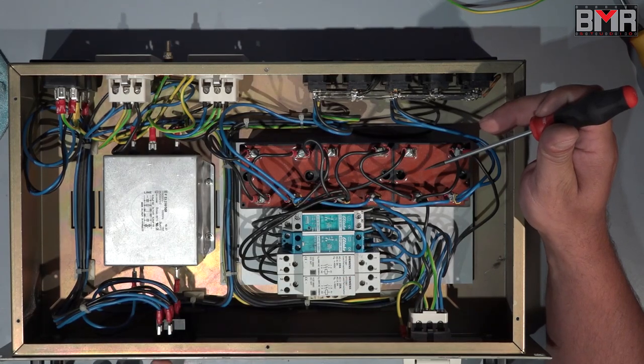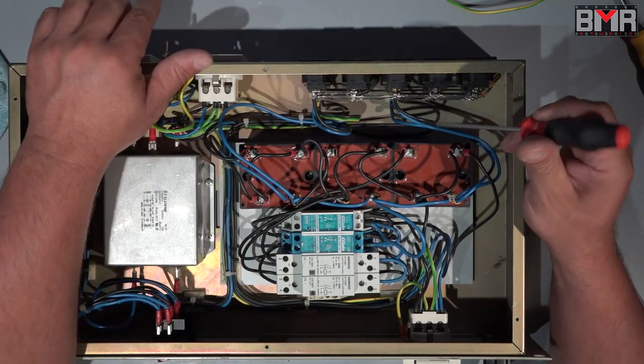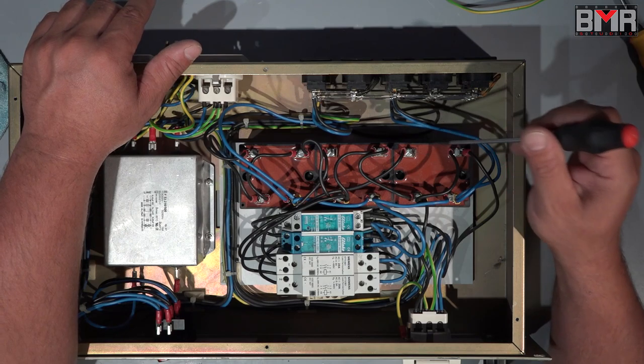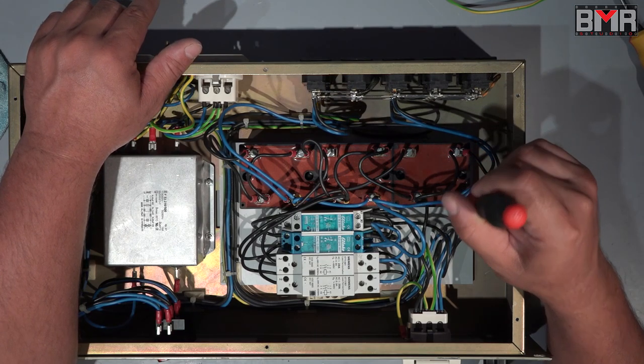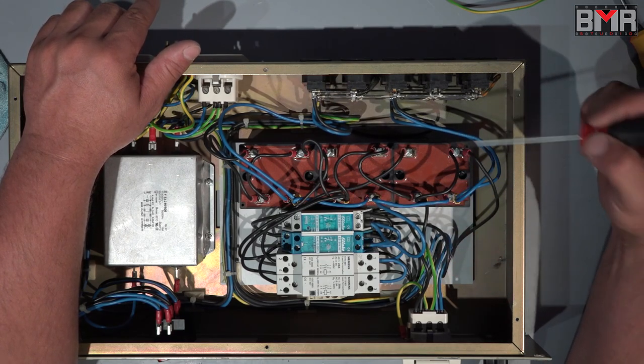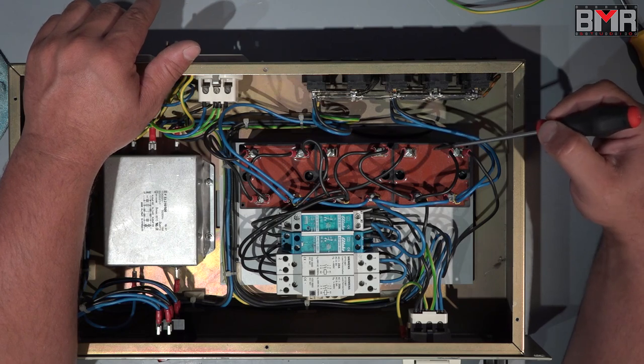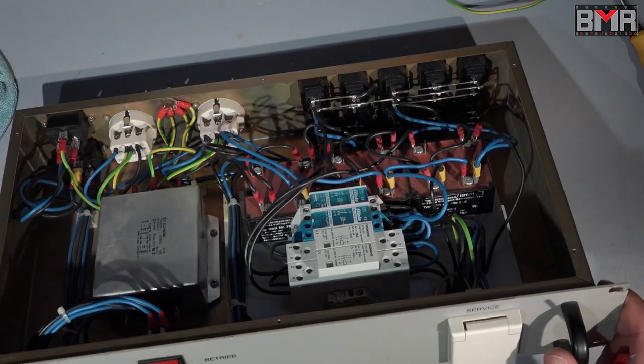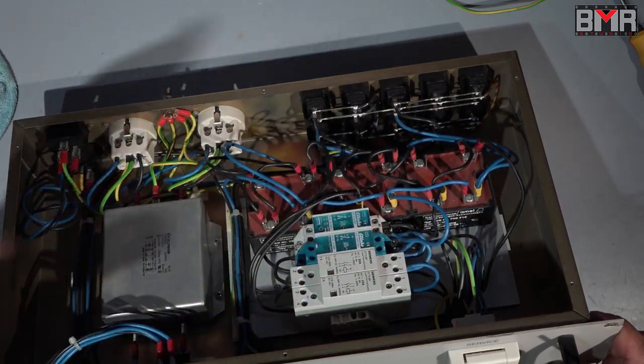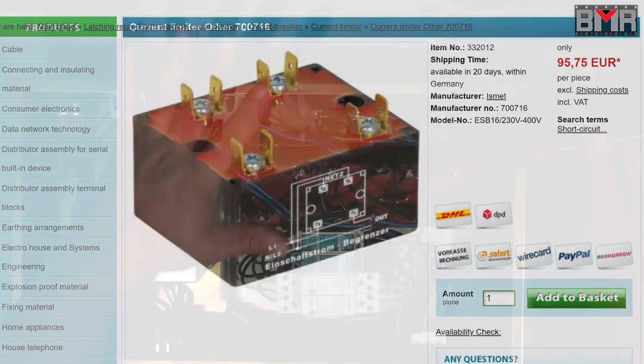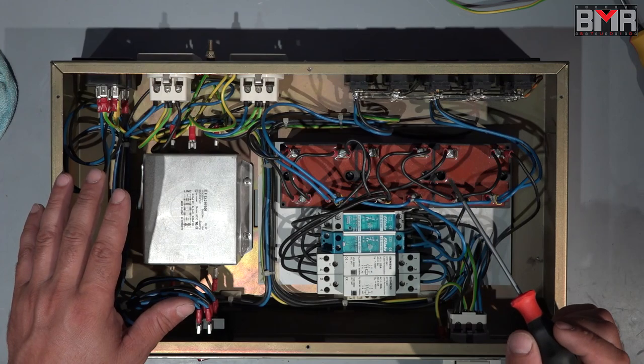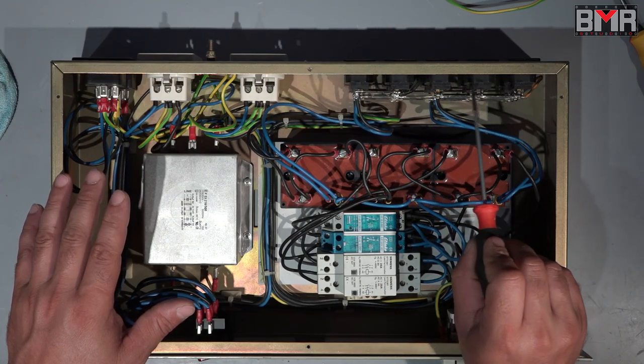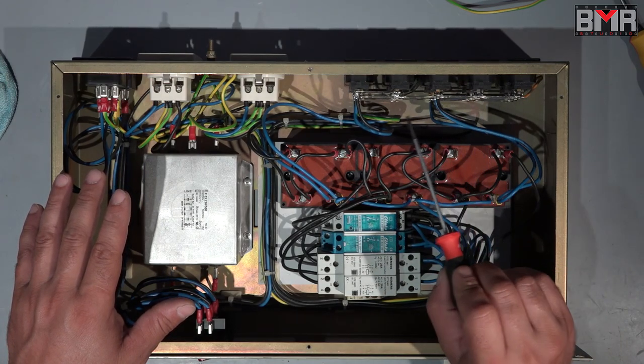Why? Because the NTC resistors, they have a magic behavior. So a normal resistor, if you heat them up, of course, you increase the resistance. Now with the NTC resistors, this is completely opposite. So as the temperature is rising, the resistance will go down. So this is how this NTC can do this really nice ramp on the beginning of the switched power. And after 50 milliseconds, of course, this mini computer here inside will short out this NTC resistor with a built-in relay. And of course, you can buy these guys nowadays from Eaton. And let me tell you, each piece costs around 100 Euro.